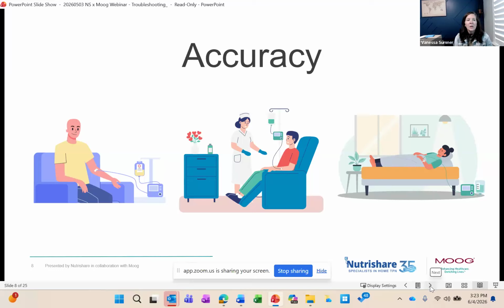But the biggest impact on accuracy is what's called head height. You may not have heard that term—I didn't know it until I started working for a pump manufacturer. Basically, pumps are calibrated at a certain head height. This will be different with each pump, but I'll use an example of 12 inches.